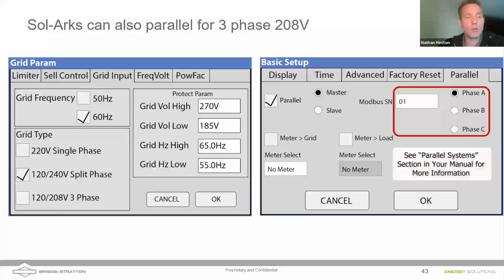And then if you want to do a balanced 3-phase output, you can do 3, 6, 9, 12 inverters for that. Your grid parameters there, these are the parameters that you're going to be high and low, so you'll accept that grid input under these parameters. If you want to have a wider tolerance, you can add it there. So if you live in a location where you have challenging grid conditions, you can modify that there.